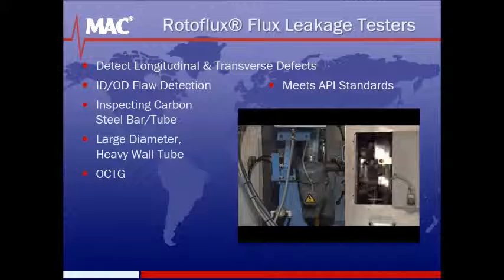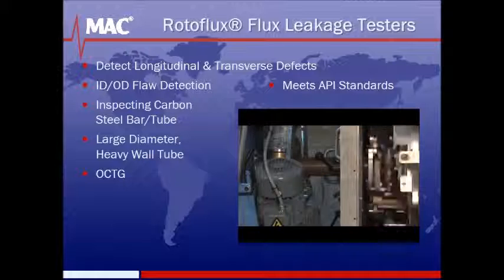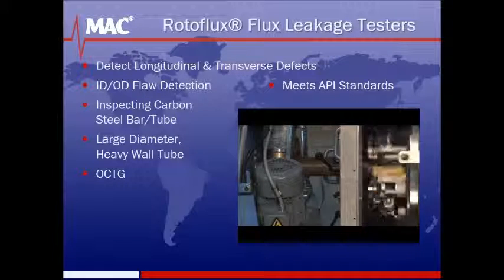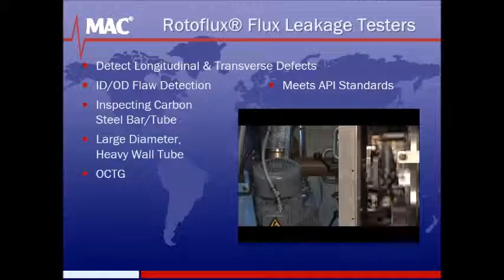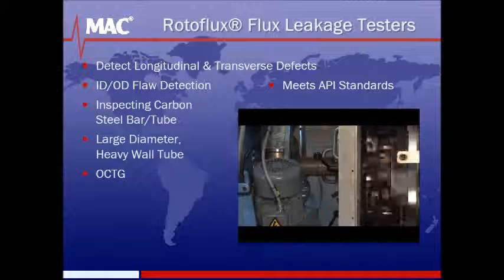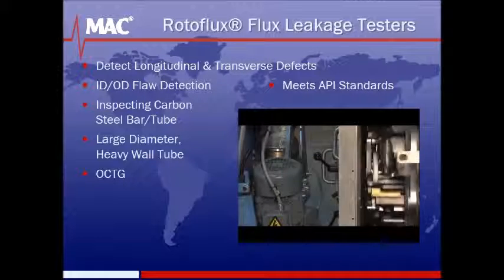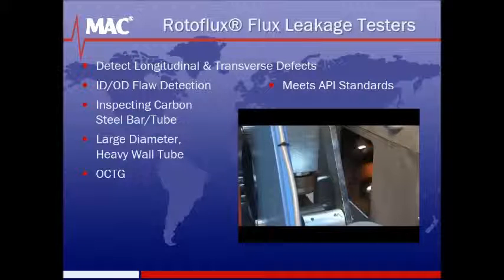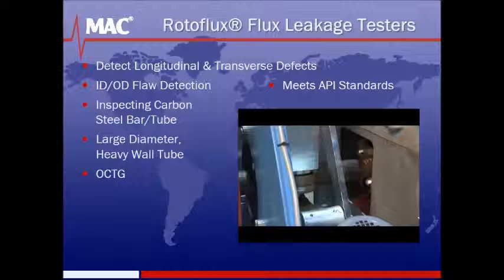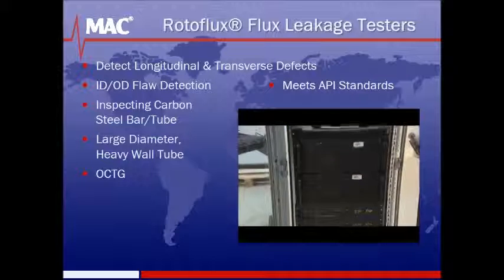To detect longitudinal defects, the material under test is driven through rotating head plates that include transverse magnetizing coils and test probes. MAC also offers Rotoflux systems to detect transverse defects, where the magnetizing poles are placed in a fixed position perpendicular to the axis of the material under test, and the sensors are rotated around the test piece. Typical applications include the detection and differentiation of ID and OD defects in heavy wall magnetic tubing and tubular products such as oil well pipe.